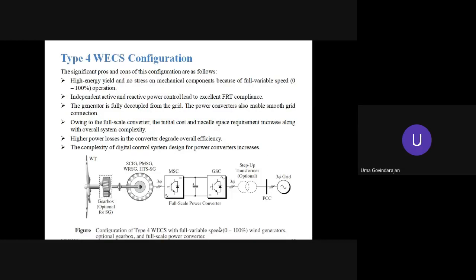Okay. The last, the type 4 configuration, the significant pros and cons of this configuration are high energy yield and no stress on mechanical components because of full variable speed. And it is possible to have independent active and reactive power control, and hence it is possible to have excellent fault ride-through compliance. It offers an excellent fault ride-through capability.